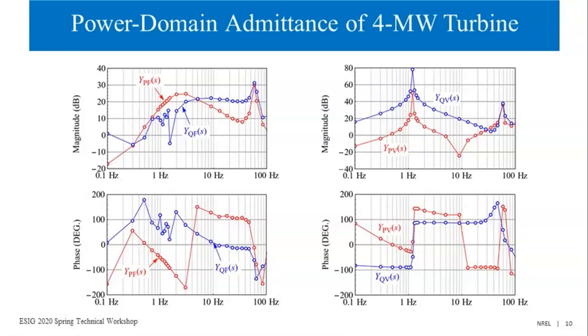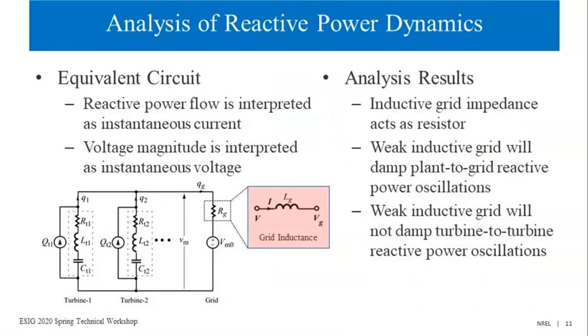In the next slide, I will show how we can analyze this kind of oscillation in a very simple manner. If we interpret reactive power as instantaneous current and the voltage magnitude as instantaneous voltage, we can represent the reactive power dynamics through the equivalent circuit that you see on this slide. On the left, the two RLC branches represent two turbines supplying reactive power output. What is very interesting is that an inductive grid behaves like a resistance in terms of reactive power dynamics. For an inductive grid, if you push in more reactive power, the voltage at the point of interconnection will increase. That is a direct proportional relationship.